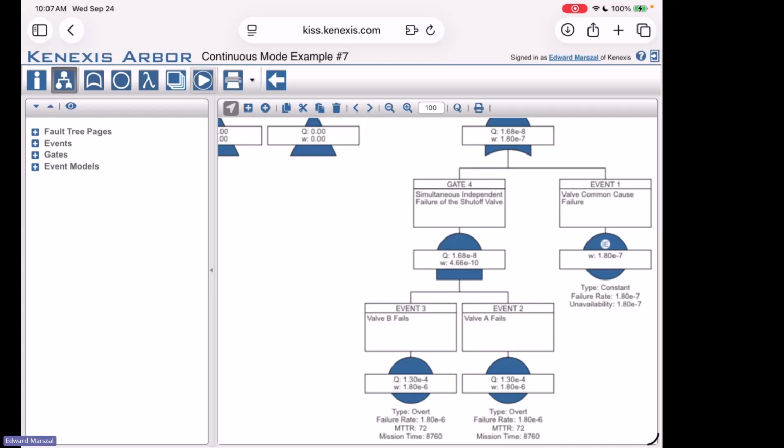So that makes sense. That math can get a little bit interesting. But even with a high demand mode, let's talk a little bit about what happened in the standards committee meetings when they made the simplification, because the 2003 version of the 61511 standard said you're in a high demand mode if your challenges are frequent in comparison to testing.